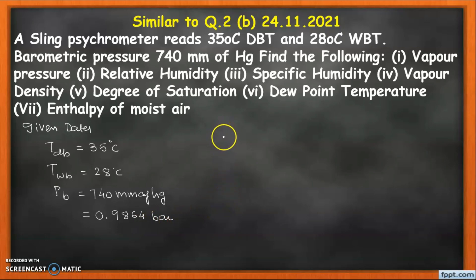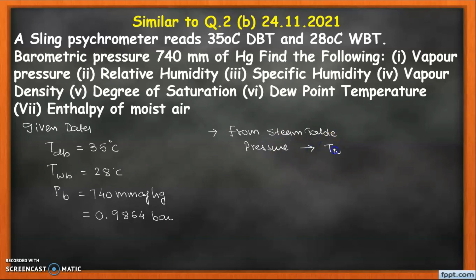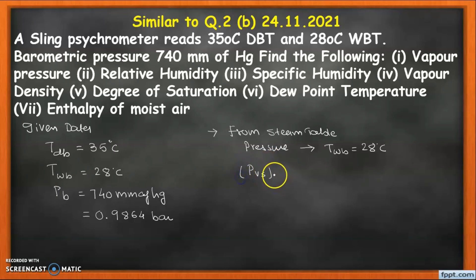Step one is to calculate the vapor pressure using Carrier's equation. For Carrier's equation we need to find the vapor pressure corresponding to the wet bulb temperature. From the steam table, we look up the saturation pressure at the wet bulb temperature of 28 degree centigrade, and we get the saturated pressure at wet bulb temperature as 0.0378 bar.